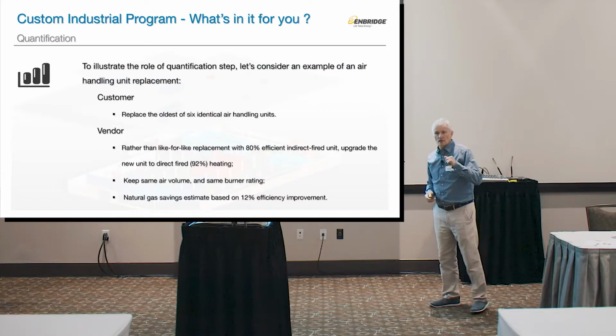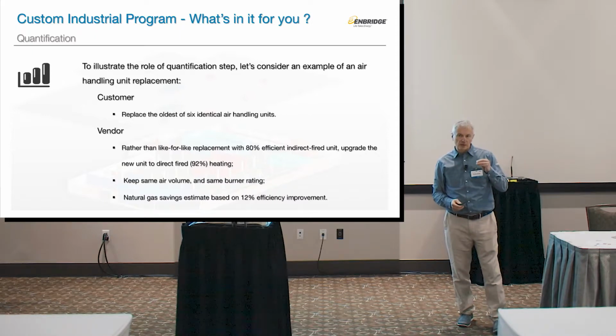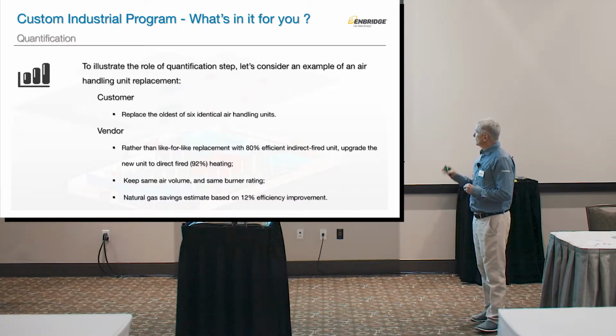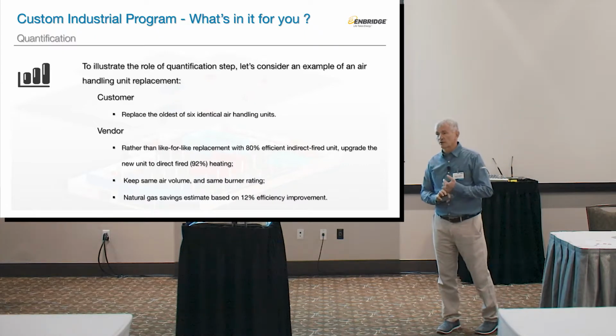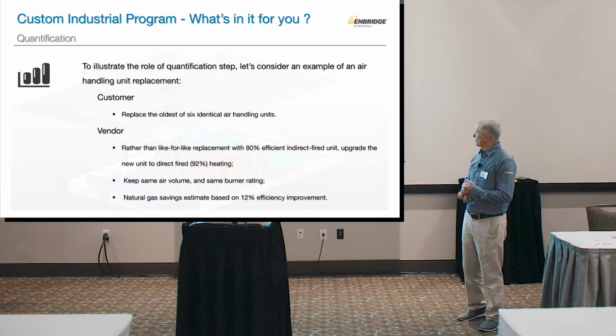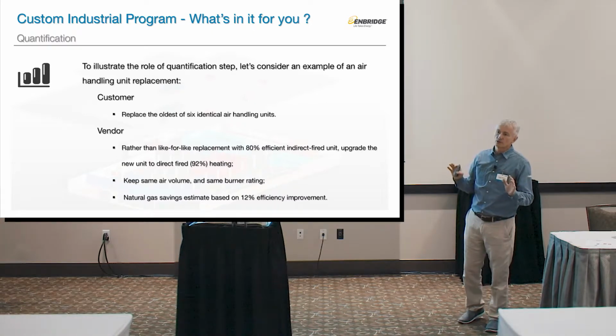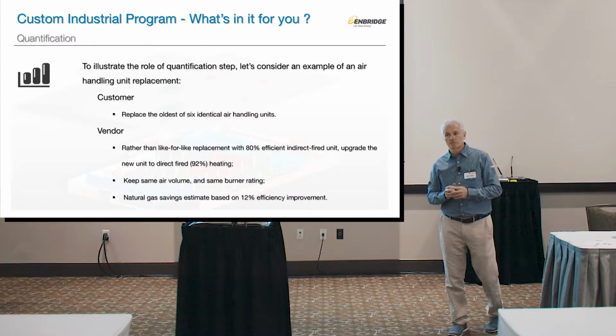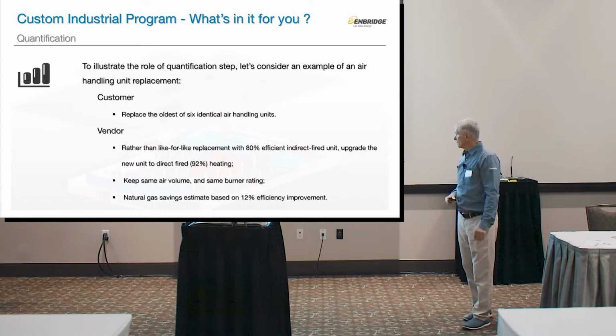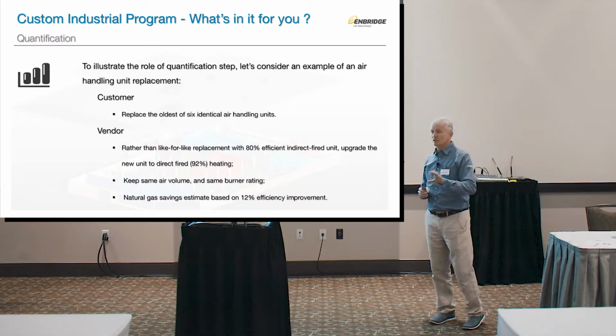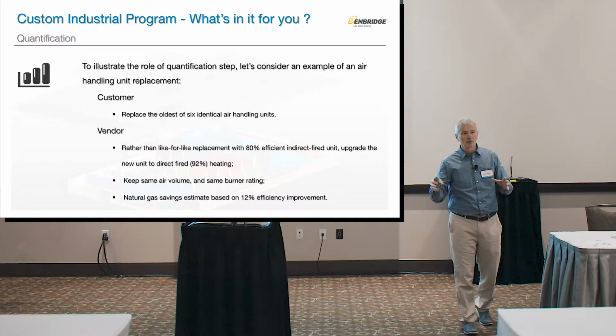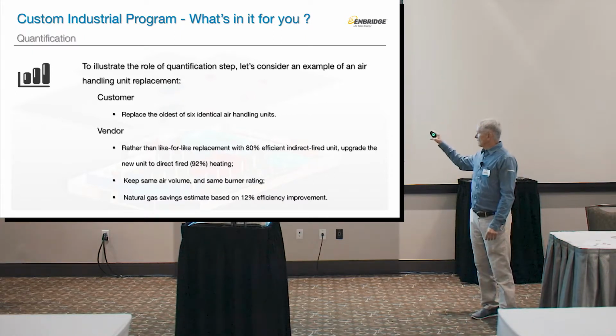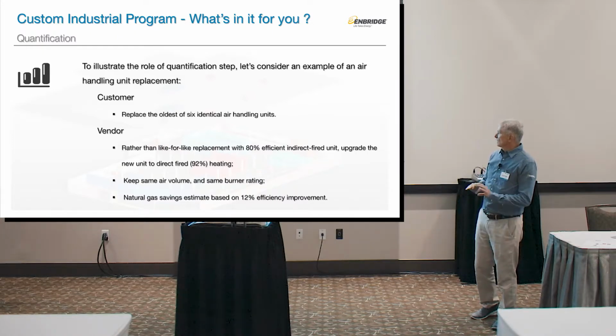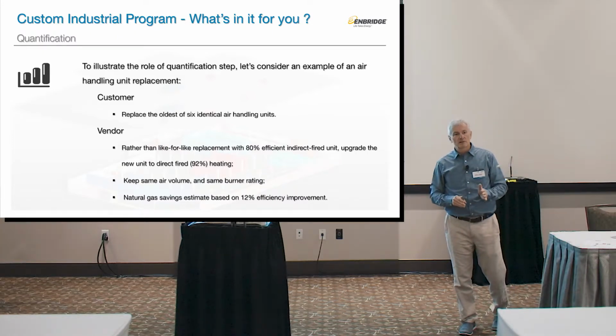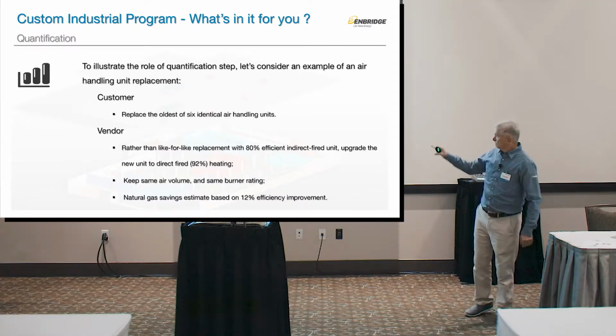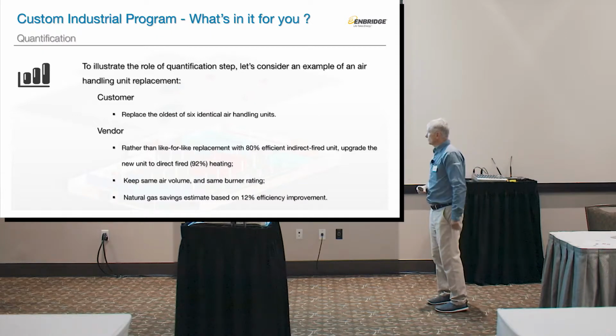Let me give you an idea of the role of the quantification step and why it's important. We dealt with a customer who wanted to replace the oldest of 6 identical air handling units at their facility. That was my customer years ago. They came to me wanting to do that. The vendor said, don't use an 80% efficient indirect fired unit like they had, put in a new one that's direct fire heating at 92% efficient. Keep the same air volume, therefore you'll get 12% savings because efficiency is 12% better. Sounds good. Looks good. Okay, so we got involved and took a look at it.